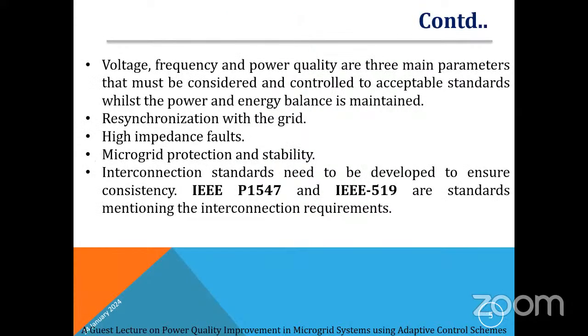So what are the problems in the microgrid system? If you see the microgrid system, we have several types of problems. Mainly, we have to control the voltage, frequency, and power quality. And also, we have several problems such as grid synchronization, high impedance faults, protection, and stability. In a microgrid system, particularly, we have to mainly control three main parameters: voltage, frequency, and power quality. These are the important parameters we have to control. Otherwise, we can't connect the renewable energy system or microgrid system to the utility grid. We have to maintain these parameters within the IEEE standards or IET standards or any international standards. Based on the IEEE 519 and IEEE 1547 standards limits, we have to maintain the interconnection standards within the ranges.